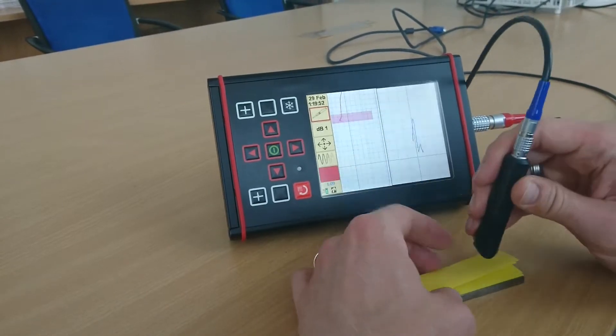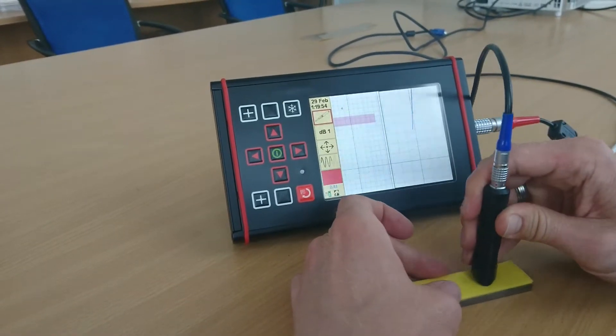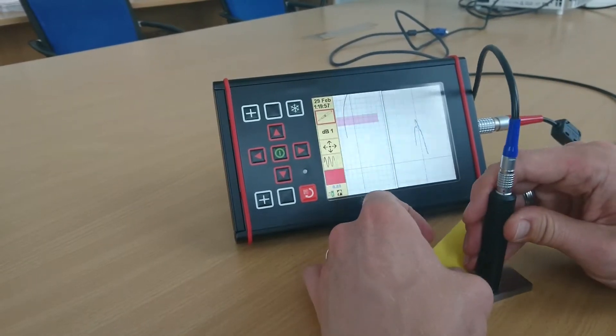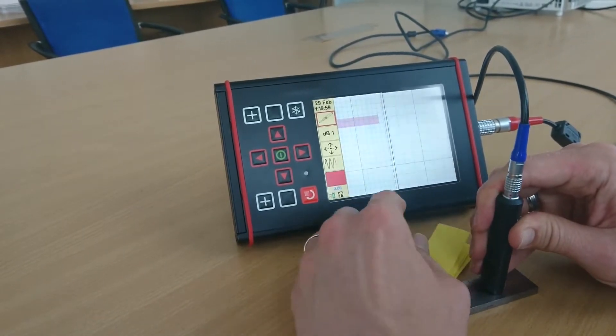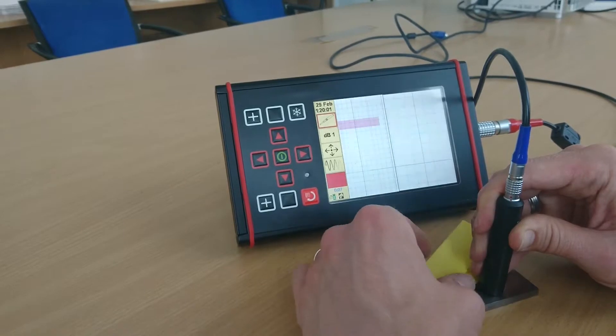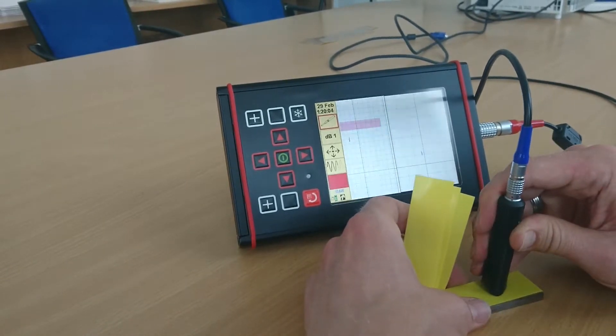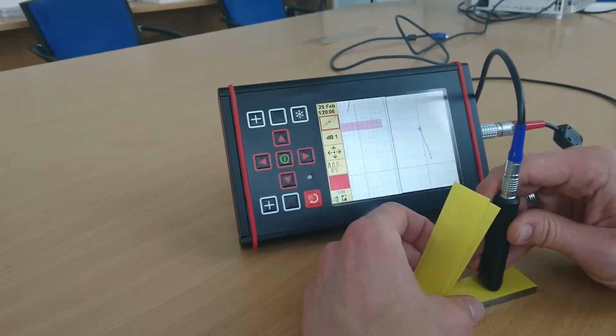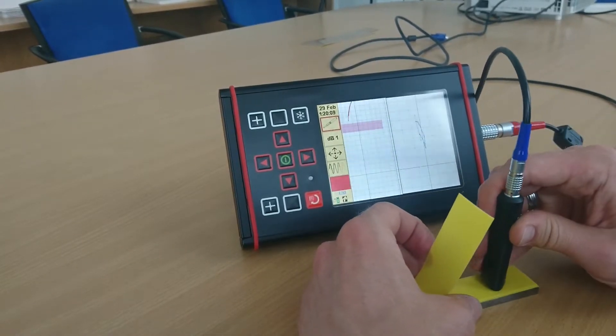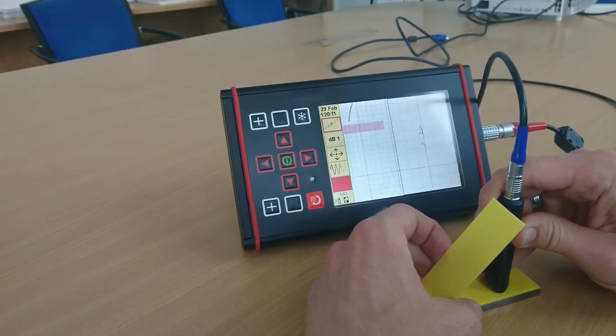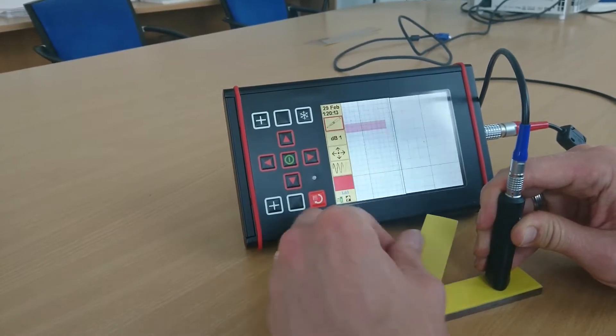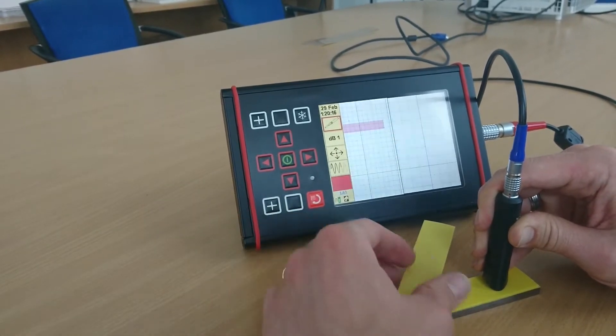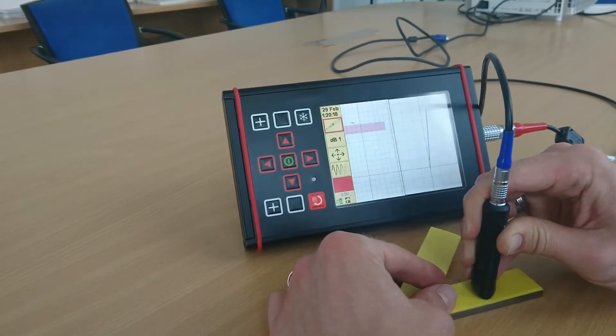The reason for the signal going high is, as you can see, without a shim, the balance point is at the origin. With the shim, it suddenly starts to go high, which is an unfortunate real world situation. So we can balance just the defect channel with the bottom balance button.